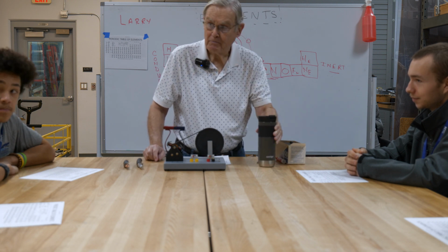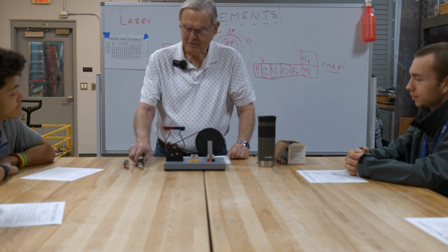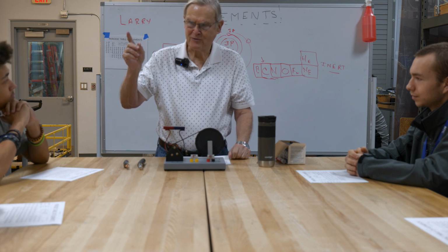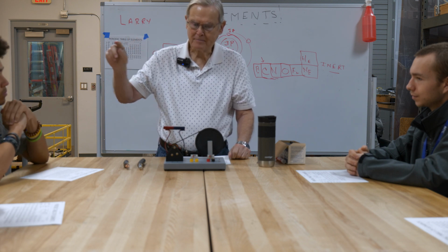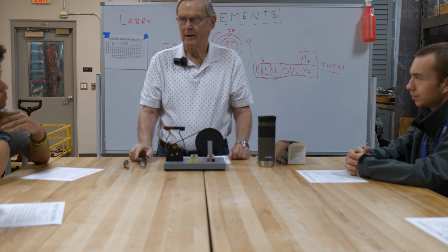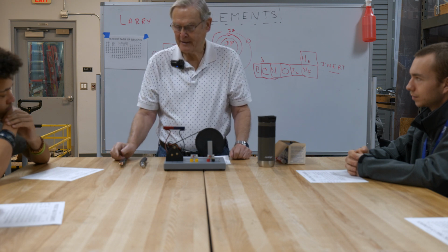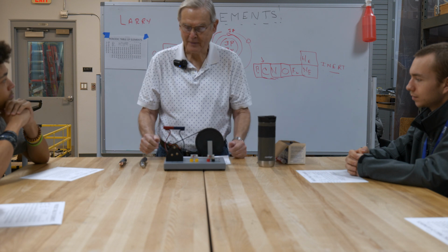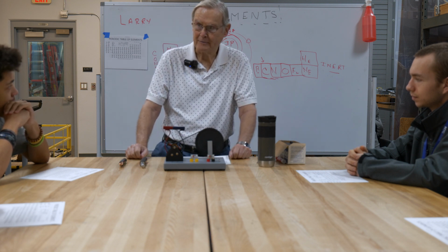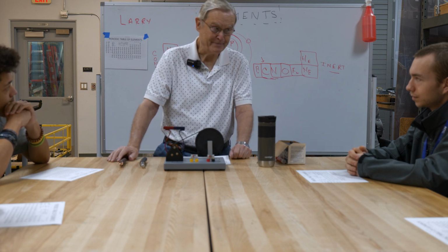What do you use aluminum for? Is it just that they used to use it in the past or something? They just kept it? Where you'll see it is the conductor that the power company installs from your transformer that sits up on the pole, and they run a service to your meter. That wire is likely to be aluminum wire. We use copper for most everything. You're going to see up to 480 volts. That's as high as we go, 480 volts. That'll all predominantly be copper wire for obvious reasons. It's malleable, and it's cheap, and it's good.